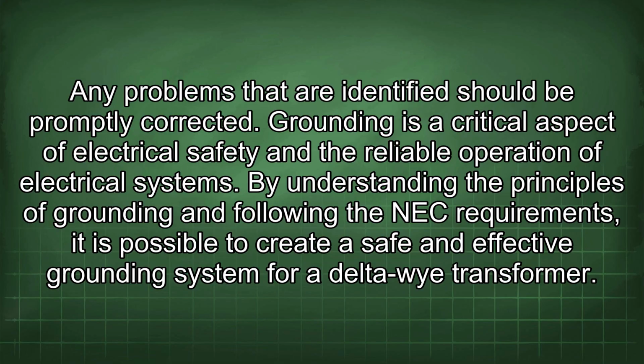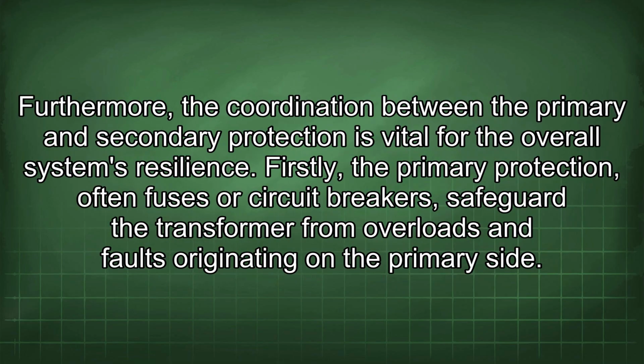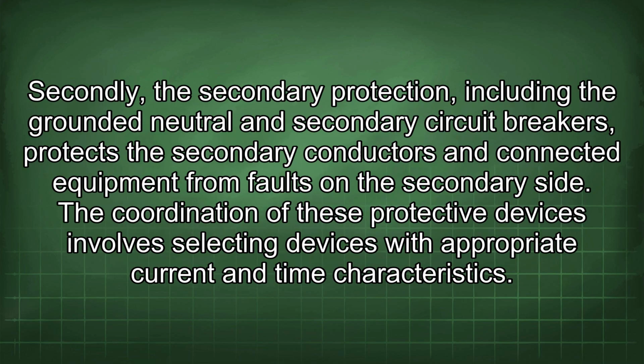Grounding is a critical aspect of electrical safety and the reliable operation of electrical systems. By understanding the principles of grounding and following the NEC requirements, it is possible to create a safe and effective grounding system for a Delta-Wye transformer. Furthermore, the coordination between the primary and secondary protection is vital for the overall system's resilience. Firstly, the primary protection, often fuses or circuit breakers, safeguards the transformer from overloads and faults originating on the primary side. Secondly, the secondary protection, including the grounded neutral and secondary circuit breakers, protects the secondary conductors and connected equipment from faults on the secondary side.